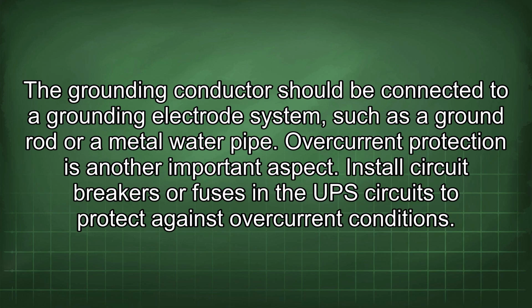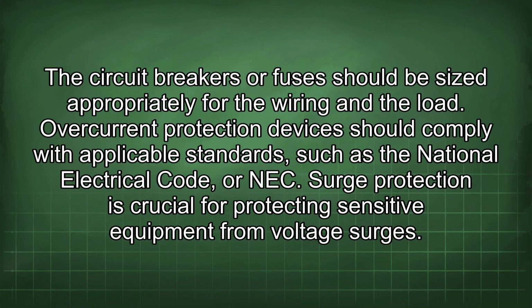Install circuit breakers or fuses in the UPS circuits to protect against overcurrent conditions. The circuit breakers or fuses should be sized appropriately for the wiring and the load. Overcurrent protection devices should comply with applicable standards such as the National Electrical Code, or NEC.